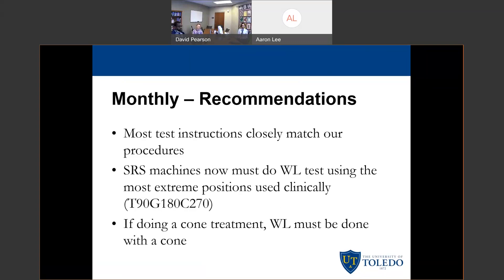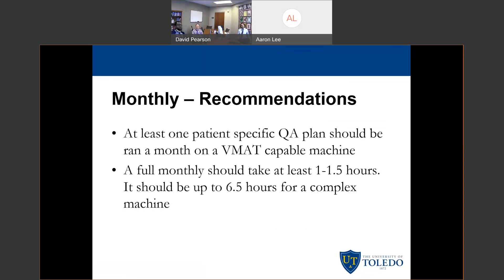If you are doing a cone treatment, the Winston-Lutz should be done with a cone, which makes sense. For the patient-specific QA, they say you should run it every month with the same exact criteria, the same exact measuring device, everything identical — just comparing to make sure it passes by the same amount as the month before. They also quantified how long the monthly should take. A full monthly should take at least one to one and a half hours for a very simple machine — say a single-series machine with two energies, KV, one photon beam, no electrons. For a relatively complex machine with onboard imaging, five or six electron energies, and five or six photon energies, they say it could take up to six and a half hours, especially if you are doing total body irradiation.